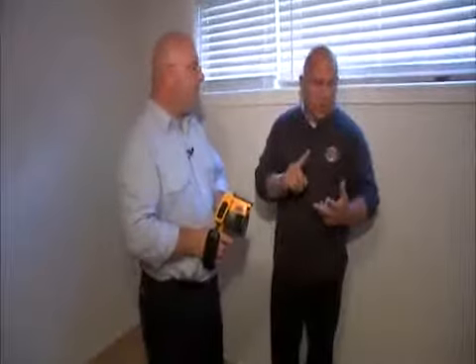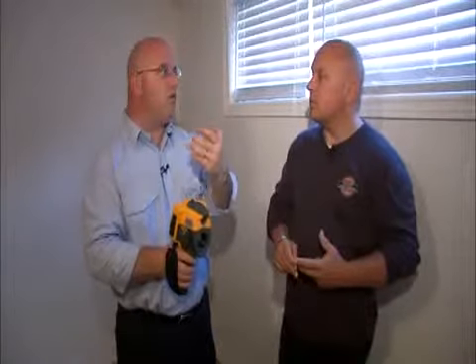So you would use this for moisture, or someone concerned about mold, possibly looking at their heating and ventilation system, whether it was functional. You had mentioned wiring — does it work with knob and tube wiring? It works with all wiring. Any wiring that's overheating is going to show up as a higher temperature than its surroundings. You still have to go to the next level and ask how hot it is — all wires under power are going to have some heat flow, that's normal, but what's determined is how high that goes. These cameras are also used for scanning electrical panels, especially in commercial and industrial systems, where you can look at the whole panel and determine if one particular breaker or connection is overheating.